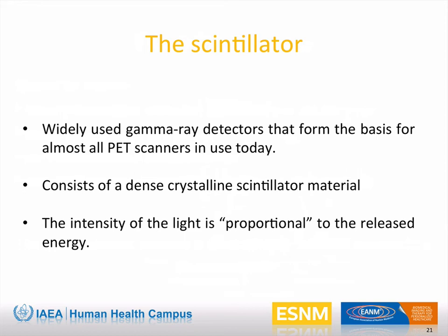For this reason, and for the relatively high stopping power, with mu at 511 keV, expressed as linear attenuation coefficient, in the range of 0.3 to 1 centimeter to the minus 1 at 511 keV for inorganic crystals, scintillators are widely used gamma ray detectors for almost all PET scanners.